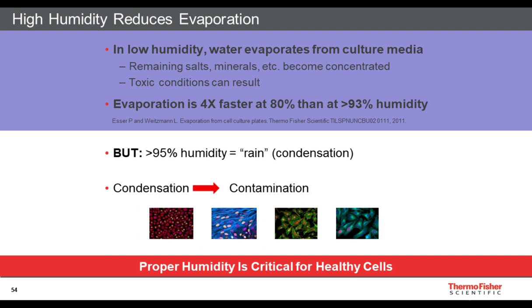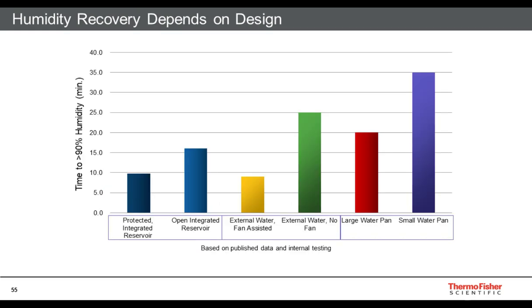So it's actually a very difficult parameter to control well, humidity. So let's look at how humidity is controlled in different systems and different incubators. Just like temperature and carbon dioxide, humidity recovery from a 30-second door opening depends on design. So this table is looking at time to recover to 90% humidity or greater following a 30-second incubator door opening.